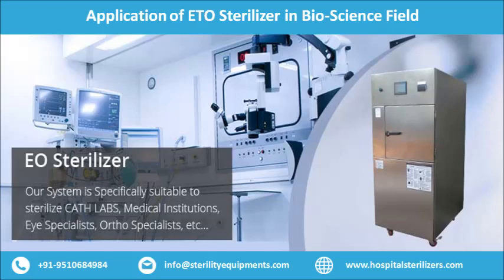Ethylene oxide sterilizer application in life science. Ethylene oxide sterilizer is used by companies in the sector of life science, like manufacturers of medical devices and various laboratories. It is strong, safe to use, and the most practical low temperature option. In the industry of biomedical research, ethylene oxide sterilizers are used to sterilize the cages and racks for reprocessing and also for various equipment.